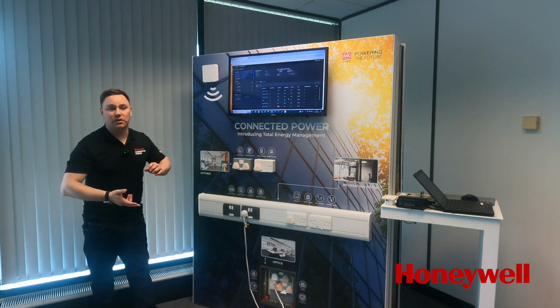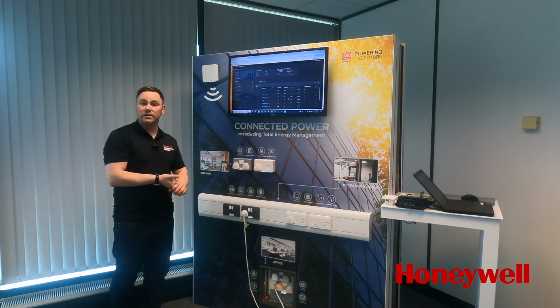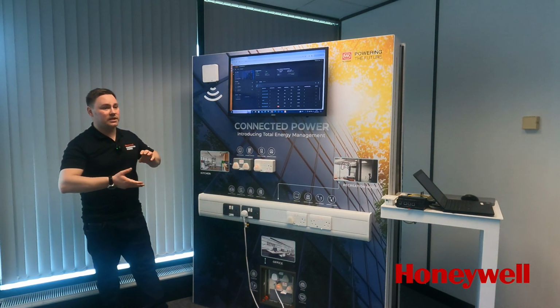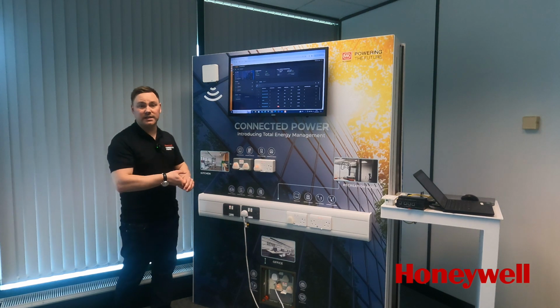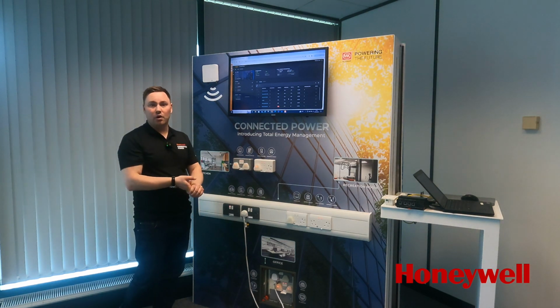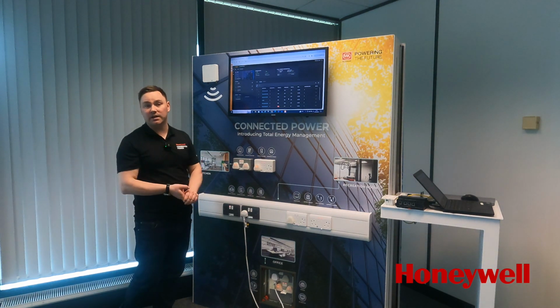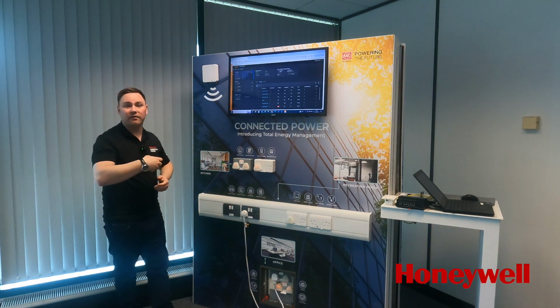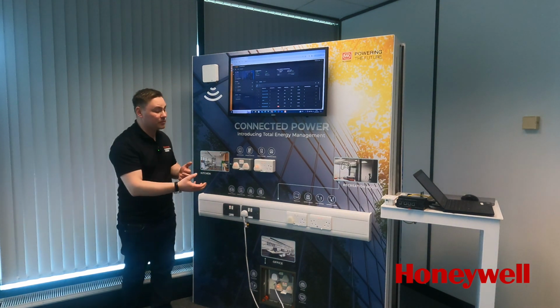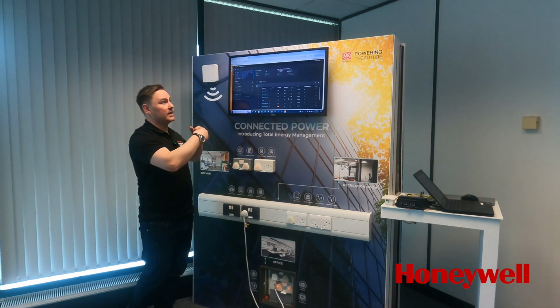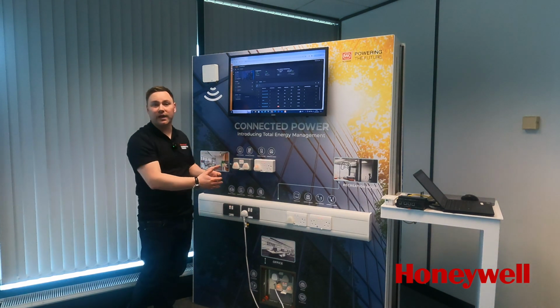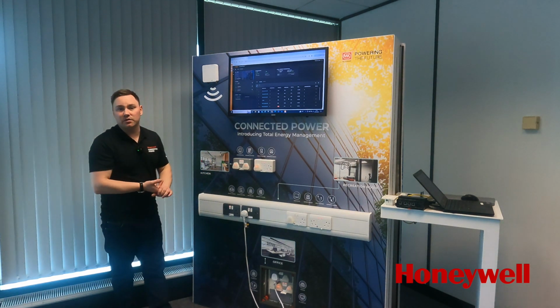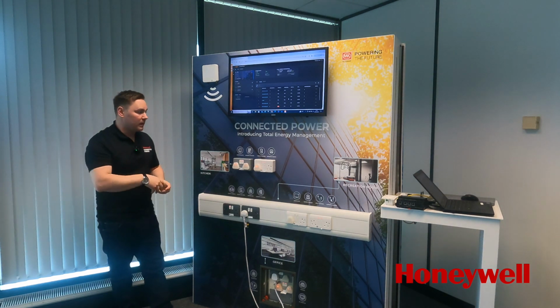This enables us to turn items off out of hours. It also enables us to have critical equipment always permanently turned on, or, for example, in waiting areas in hospitals where we have cleaners' sockets where we don't want people plugging in, we have the option as the building management system to lock that socket off so it can only be used in certain situations.